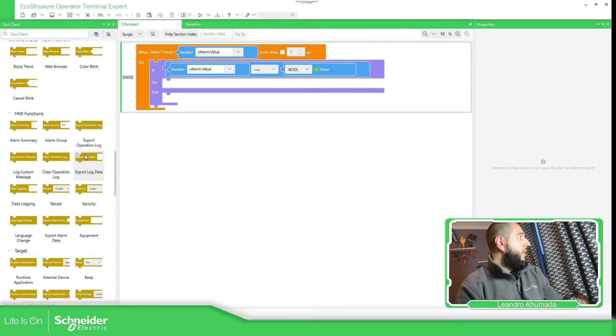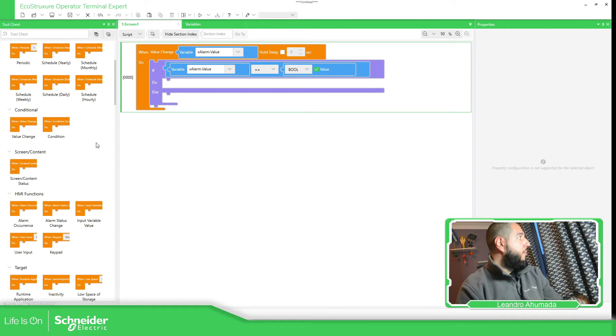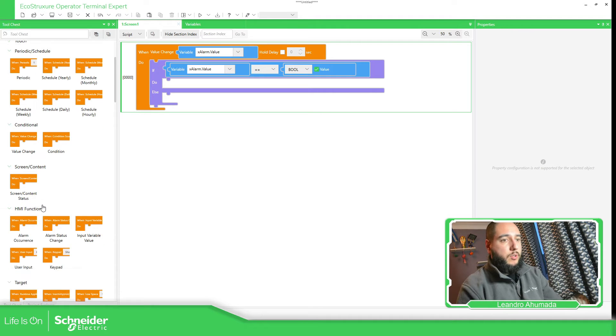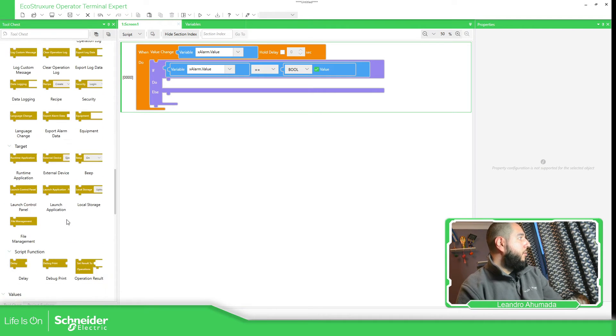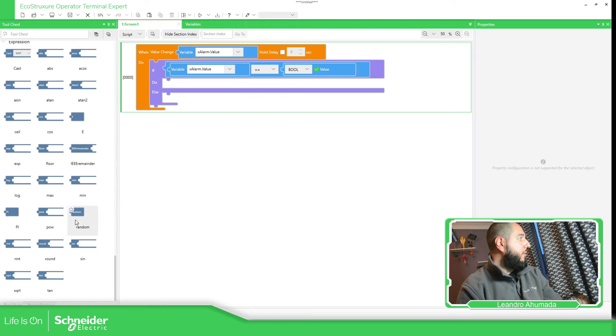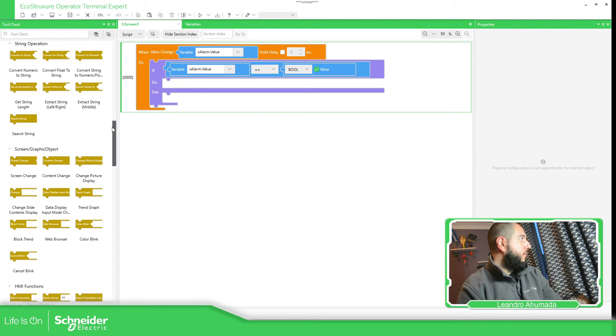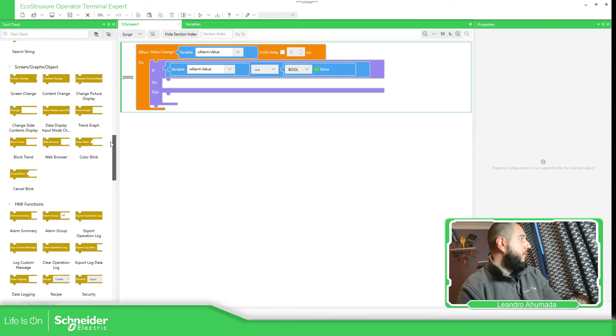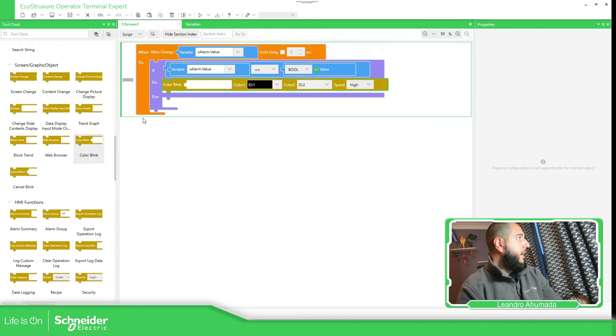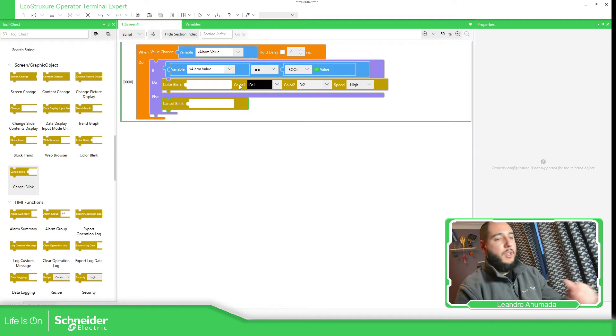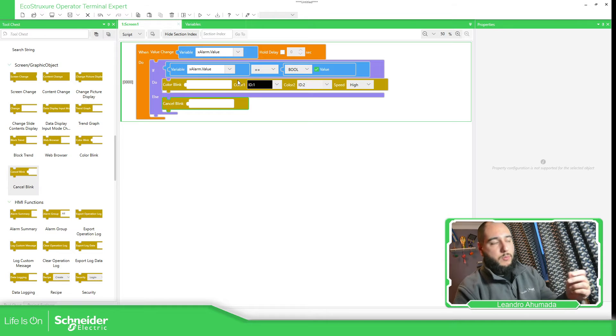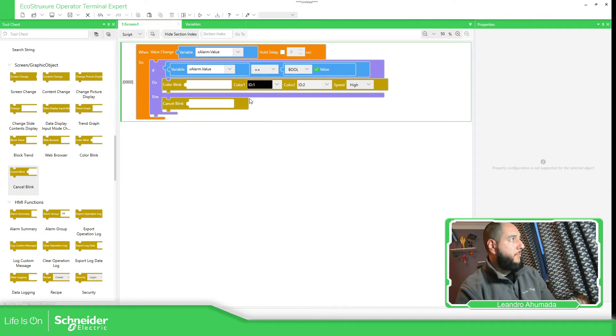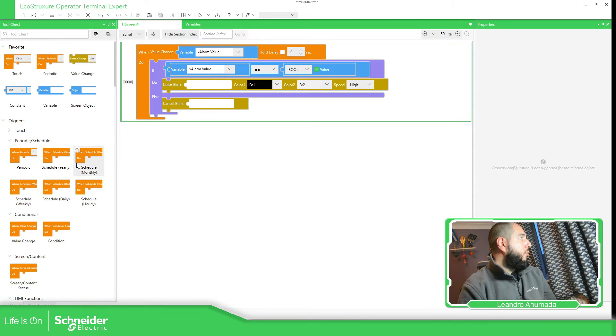So inside the block area, we have different blocks. The one particular that I want to show in this video is the one for the objects for the screen here: color blink and the cancel blink. So when we have an alarm, we set this condition to change the fill property of an object. And when the alarm is off, we cancel it.